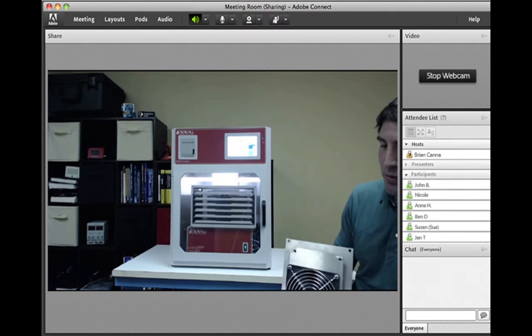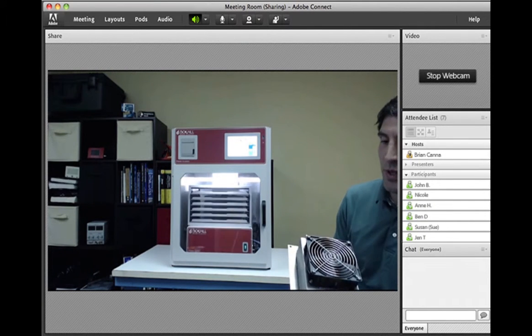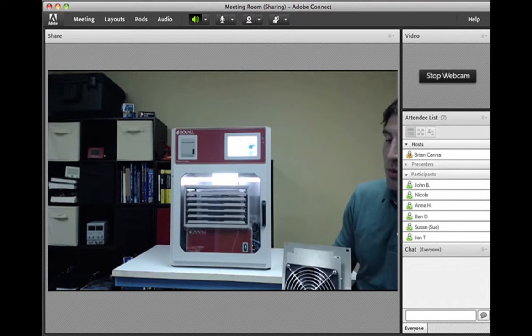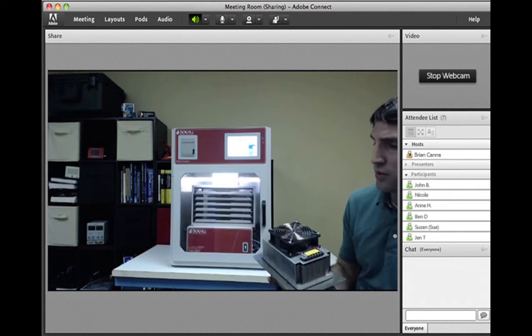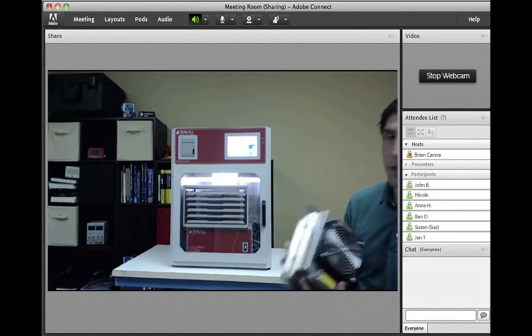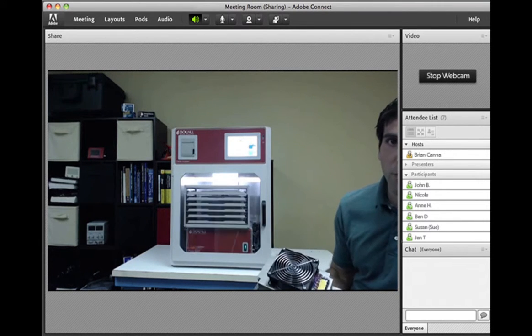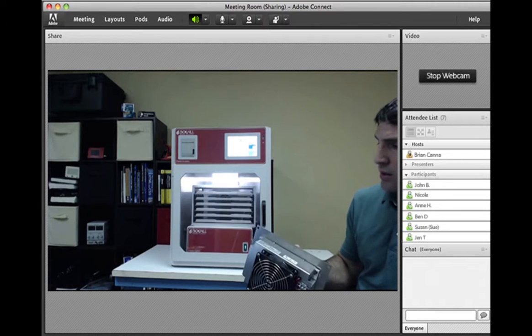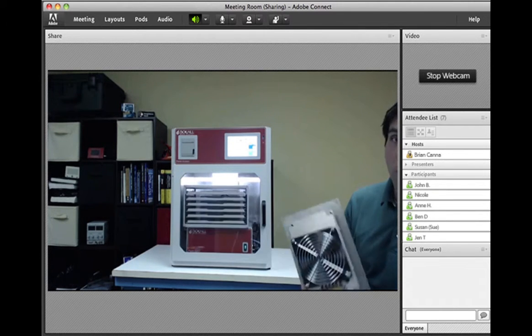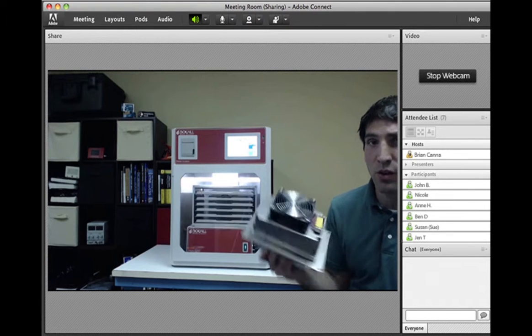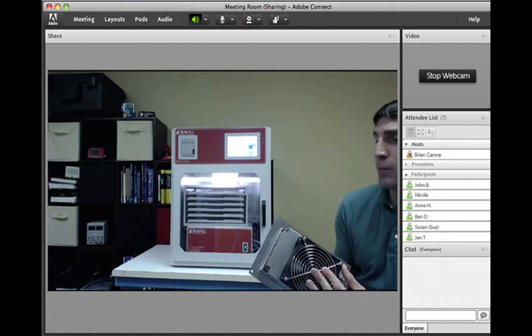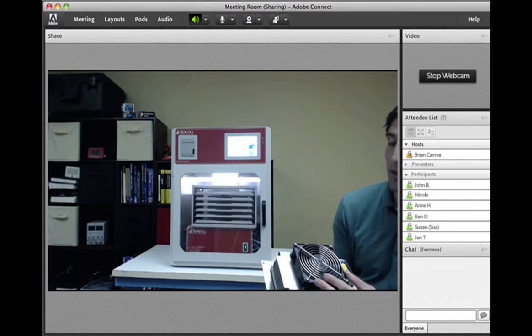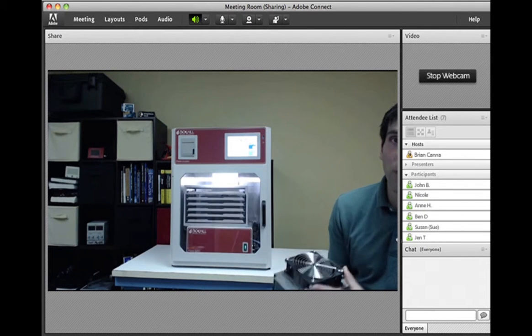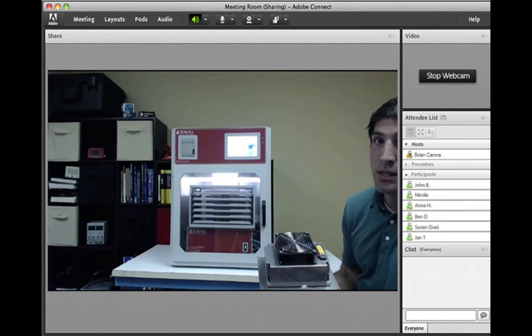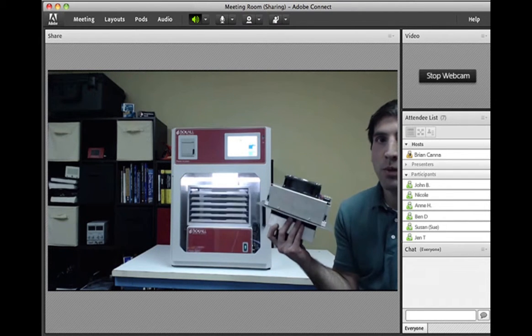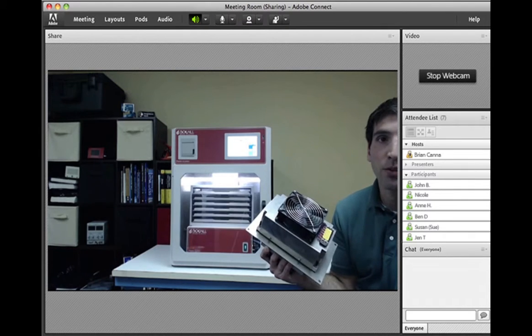We did a lot of real-world testing with these in heat chambers and high humidity to make sure that there weren't any issues, but this is actually a mission critical Peltier. They use these in a lot of power distribution boxes and military equipment, so it's a very rugged solid state device. There are no moving parts except for the fans, whereas a compressor is constantly running and has refrigerant which can leak out and has to be replaced. So it's a much more efficient, much more robust design than a compressor.